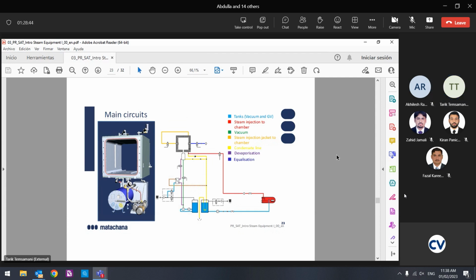Then the vacuum circuit, the green one. In the vacuum circuit we have only a valve, no return valve or one-way valve, and then the ejector and the vacuum pump. This is the direct vacuum circuit, and it's important. Then steam injection, jacket to chamber, the orange line.